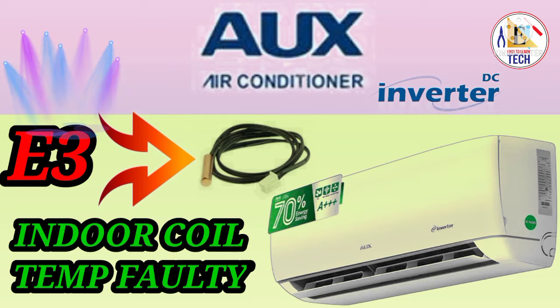Again, if you are getting the same error E3, it means you have to check the resistance of your coil sensor. If the resistance is not good, change the coil sensor. If the resistance is good, then you have to check the out supply from your indoor PCB. If the out supply is not coming properly, you need to change the indoor PCB and your unit will be in working condition.